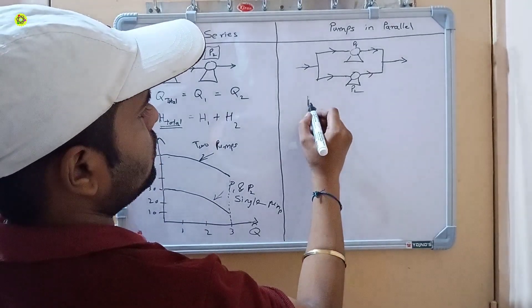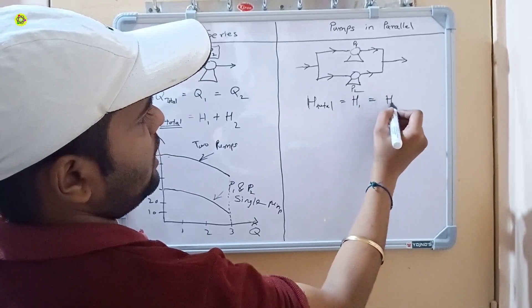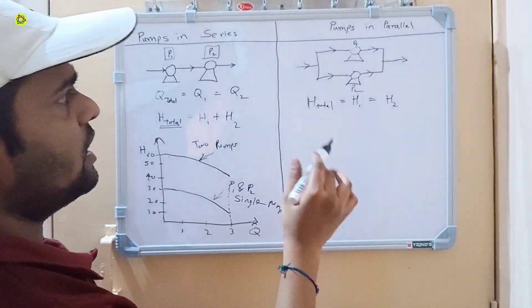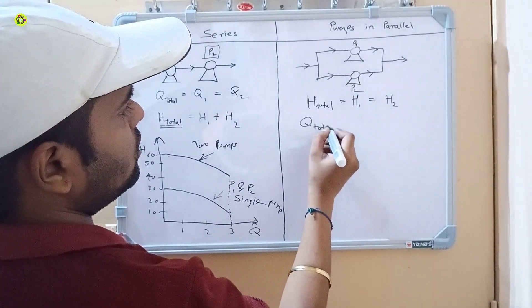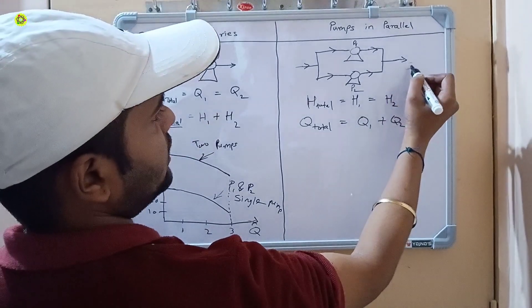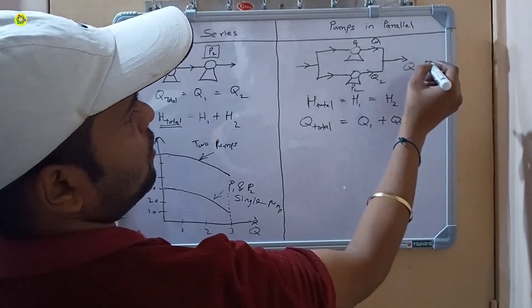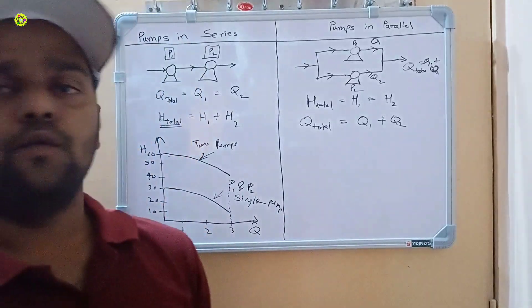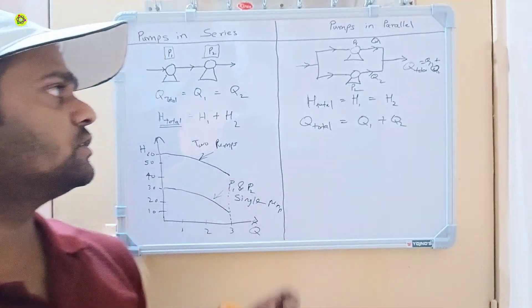In the parallel arrangement of pumps, the head is constant. Because of this arrangement, Q total equals Q1 plus Q2 — that is, the total flow rate is the sum of Q1 and Q2. We use this parallel arrangement to increase the flow rate at the output of the pumps.